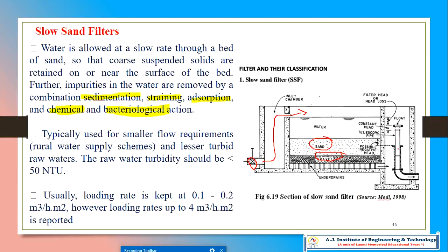This is the head. Why are we providing the head? To check the head loss, because we will come to know the filter head or head loss. This is our head loss. Once it reaches here, we have to go for back washing. It is telling us that the filtered water is not flowing through the bed.